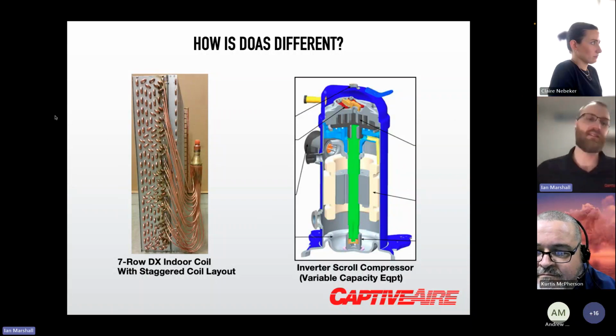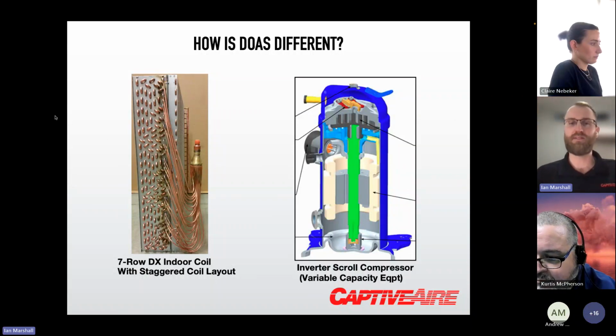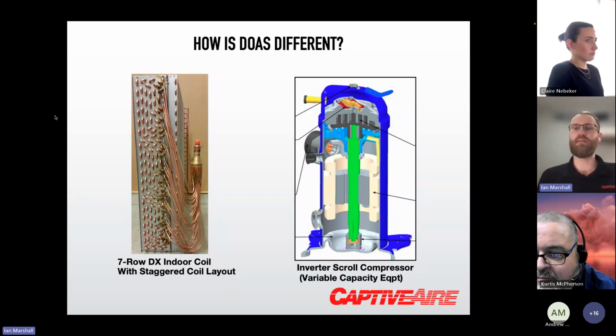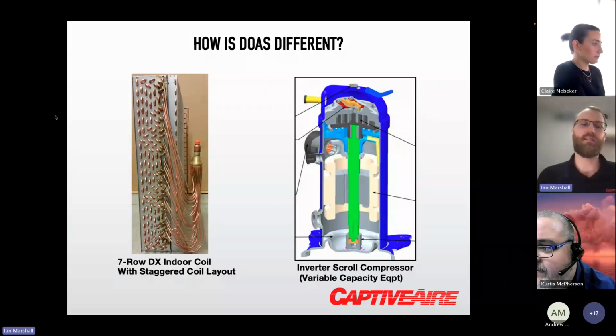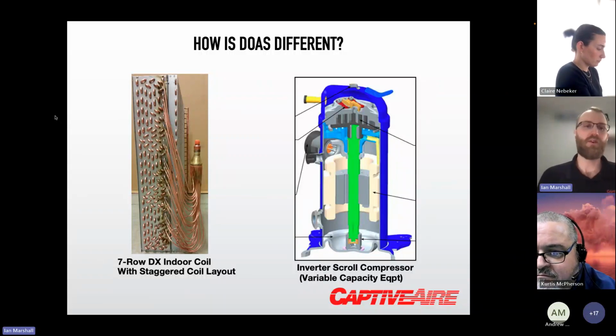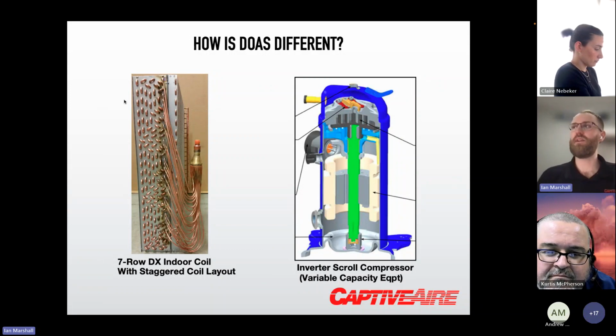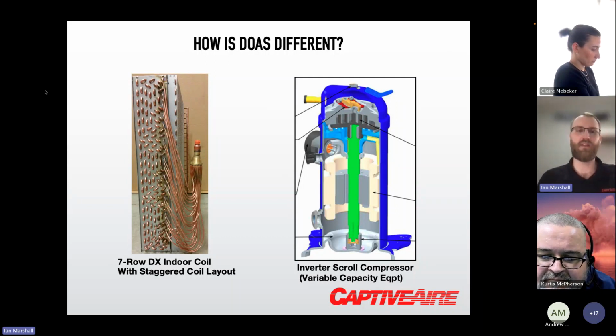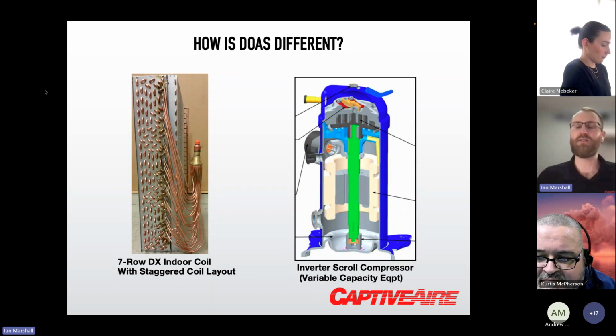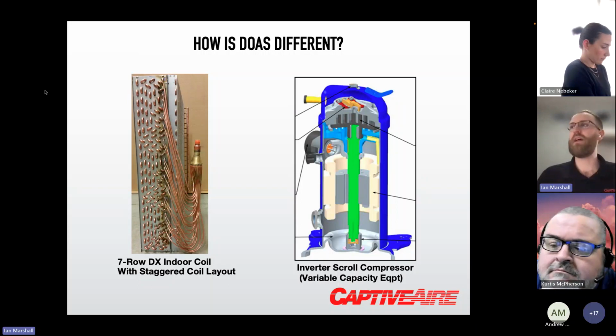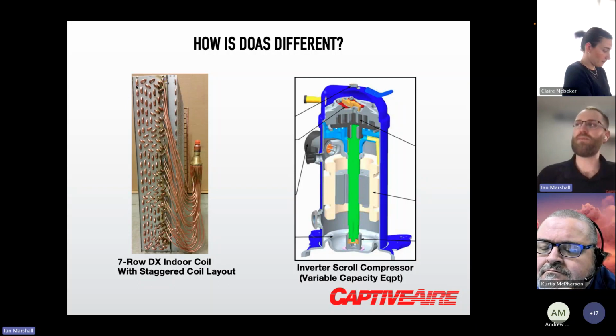So the big things that make a DOAS different in terms of components to, say, a traditional rooftop unit, and the big things that make our DOAS unique, is the first component, the indoor DX evaporative coil. We utilize a much wider or larger coil design. So you can see here, this is a 7-row coil, which is standard. We use somewhere between a 4 to a 10-row coil, just depending on the unit size. And the idea of that is to pull out as much moisture as possible from that outside air, because you could be pulling in really hot or really humid outdoor air. You need to be able to cool it down and dehumidify it. And the idea being have as much residence time in that coil to drop the temperature, to get air to touch every surface.